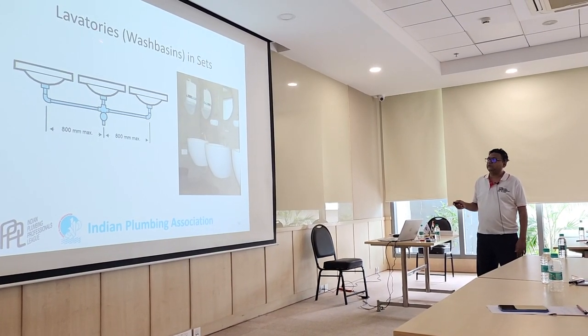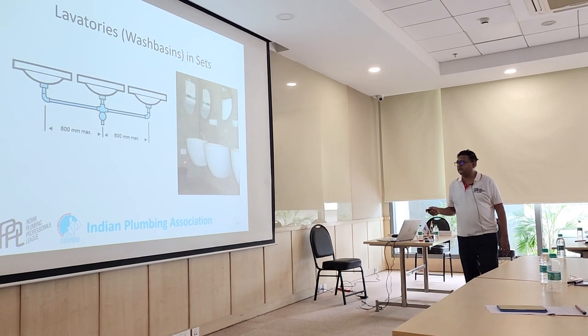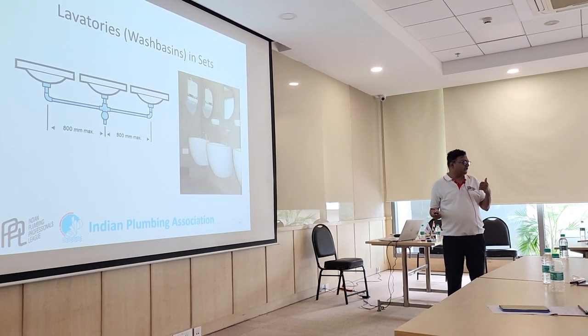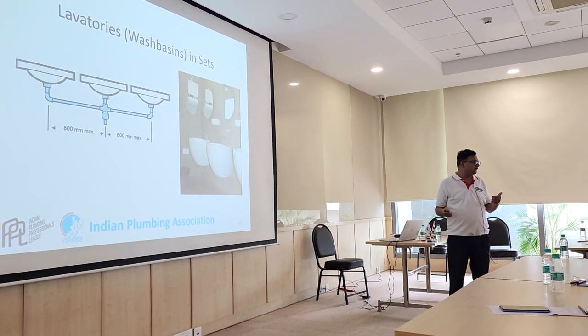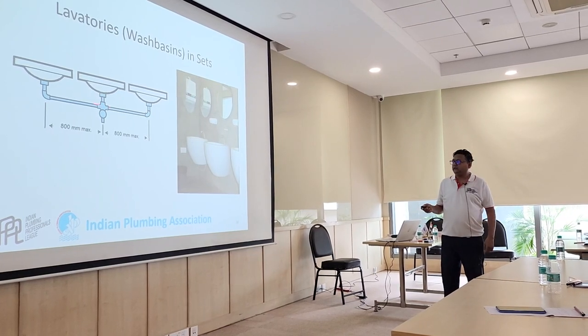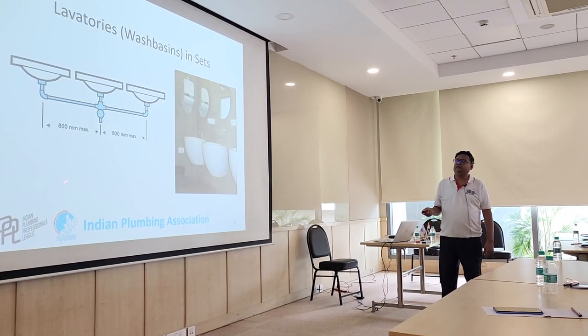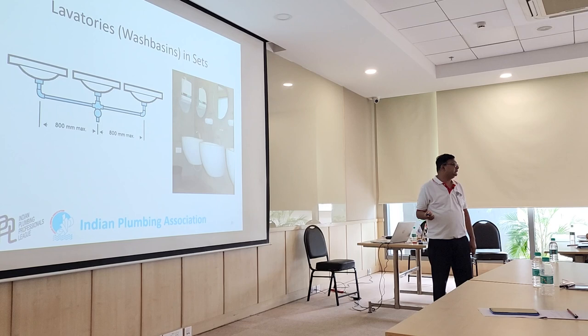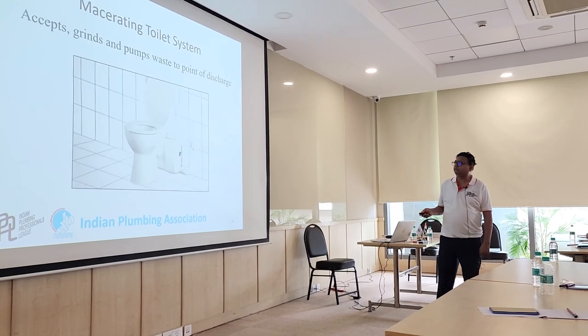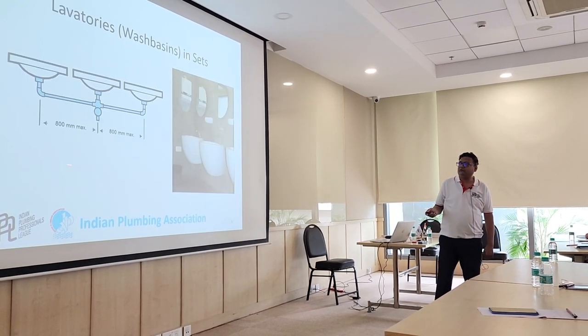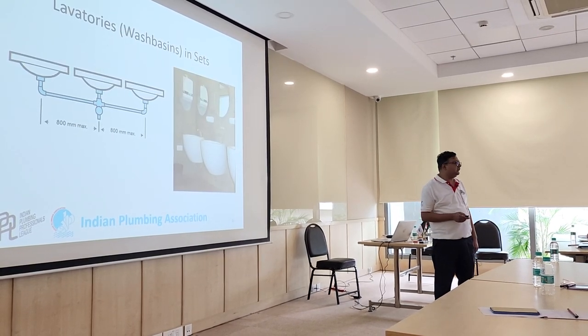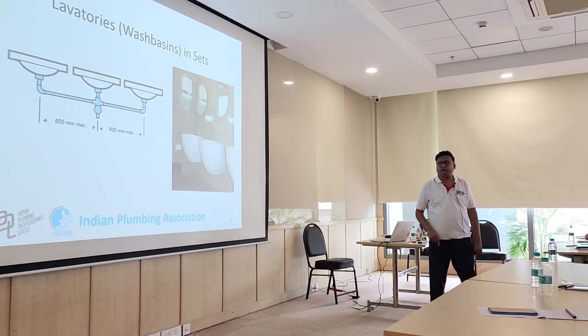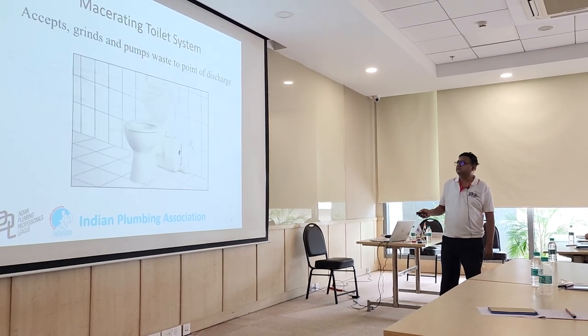What is a lavatory? Wash basins in a set of 2 or 3, as shown in the earlier slide. They are connected with a maximum distance of 800mm between them. What to do if the distance is more than 800mm? Provide a separate connection.